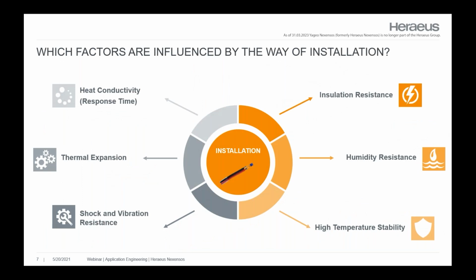So here you can see different factors that contribute to good performance of our sensors and that are also influenced by the installation of the sensor probe. We're going to talk in more detail about the heat conductivity, or as we call it, the response time, about the insulation resistance, the thermal expansion, the humidity resistance, the shock and vibration resistance, and also the high temperature stability. You can also find these terms on our data sheets.